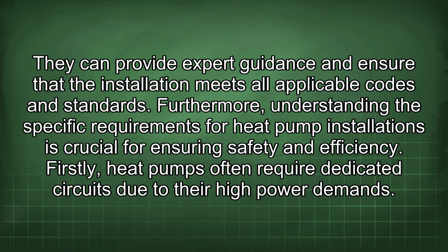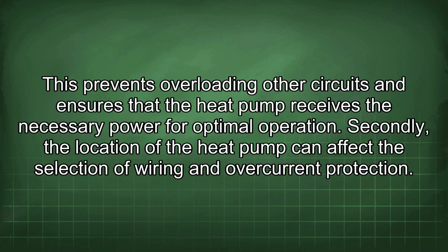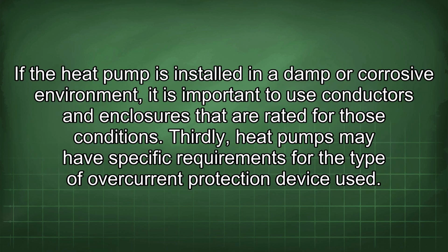Furthermore, understanding the specific requirements for heat pump installations is crucial for ensuring safety and efficiency. Firstly, heat pumps often require dedicated circuits due to their high power demands. This prevents overloading other circuits and ensures that the heat pump receives the necessary power for optimal operation. Secondly, the location of the heat pump can affect the selection of wiring and overcurrent protection. If the heat pump is installed in a damp or corrosive environment, it is important to use conductors and enclosures that are rated for those conditions.